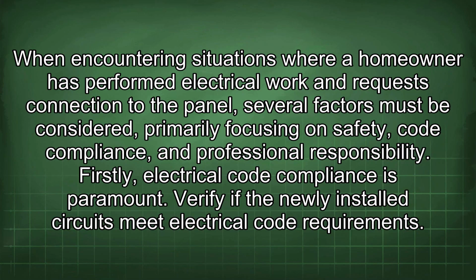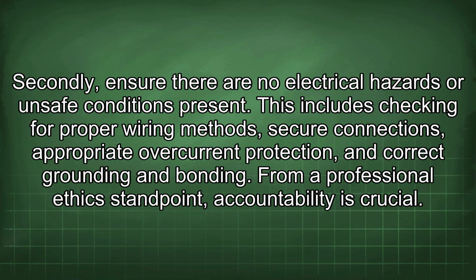When encountering situations where a homeowner has performed electrical work and requests connection to the panel, several factors must be considered, primarily focusing on safety, code compliance, and professional responsibility. Firstly, electrical code compliance is paramount. Verify if the newly installed circuits meet electrical code requirements. Secondly, ensure there are no electrical hazards or unsafe conditions present. This includes checking for proper wiring methods, secure connections, appropriate overcurrent protection, and correct grounding and bonding.